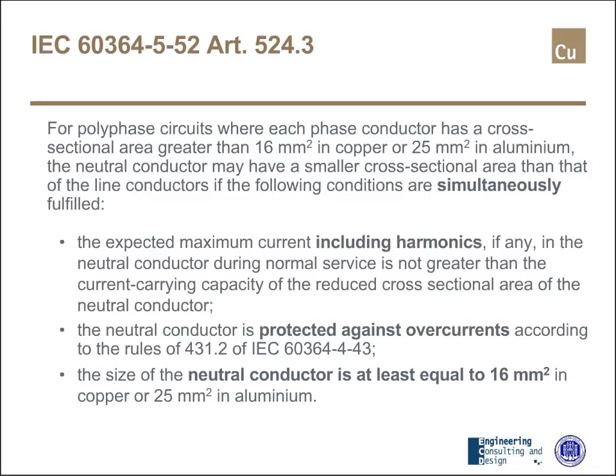We have two other conditions to be fulfilled just to reduce the neutral section. The neutral conductor is protected against overcurrent according to the rules of the same standards. And the last one: the size of the neutral conductor is at least equal to 16 mm² in copper or 25 mm² in aluminum.